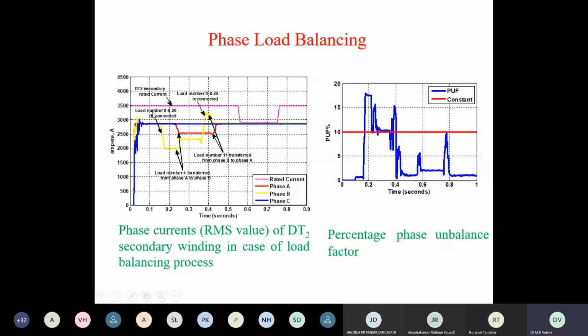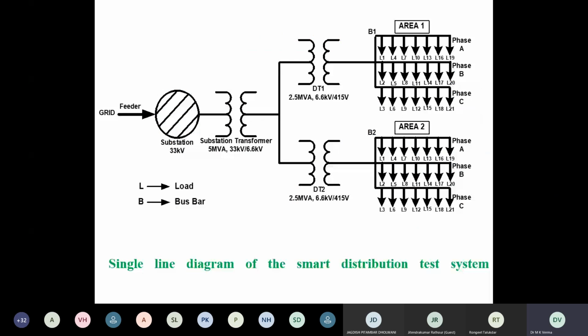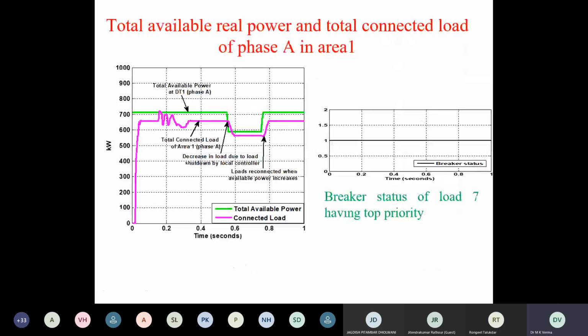Load 8 and 20 were disconnected, and due to this the system becomes unbalanced. Say 8 and 20 are connected in phase B. Earlier, all three phases were drawing nearly equal power. Now, since 8 and 20 were disconnected, it becomes unbalanced. Once it becomes unbalanced, the load balancing algorithm is run. So, based on the load balancing algorithm, what is done?